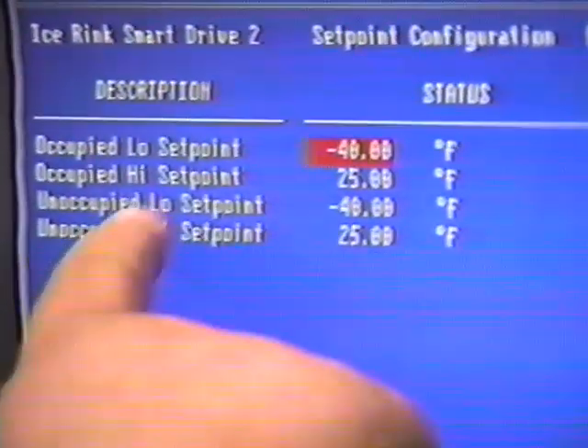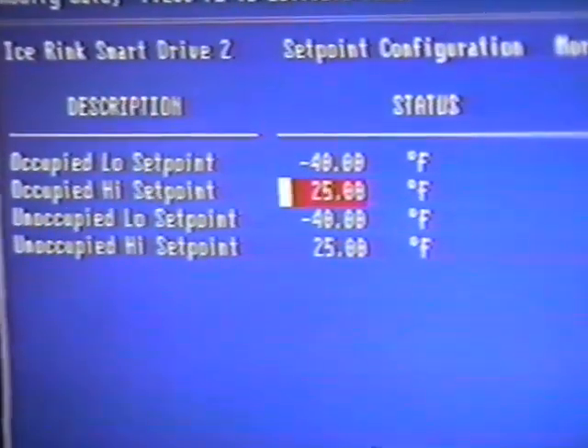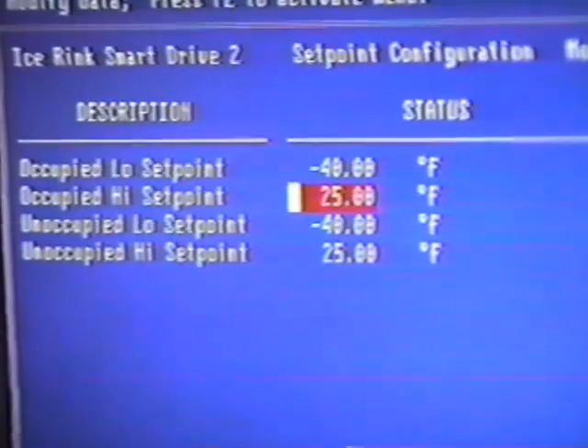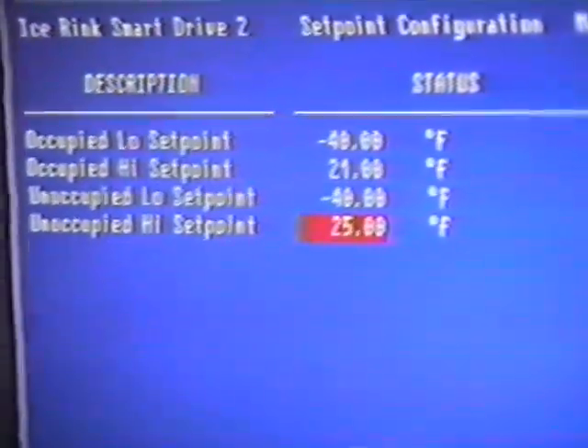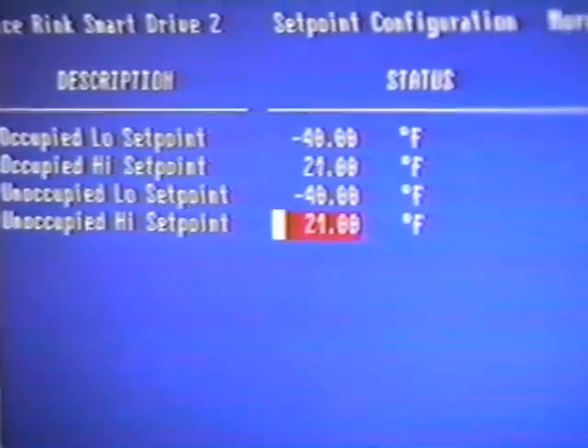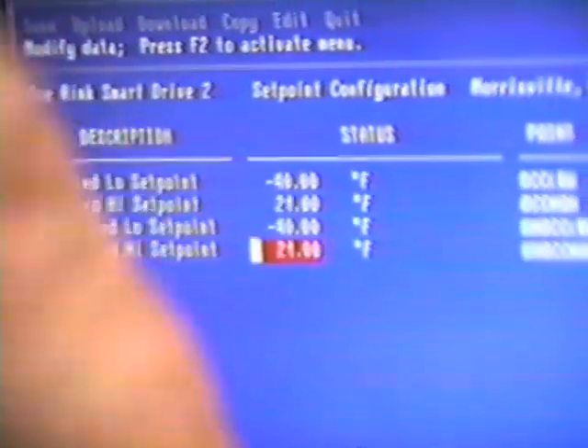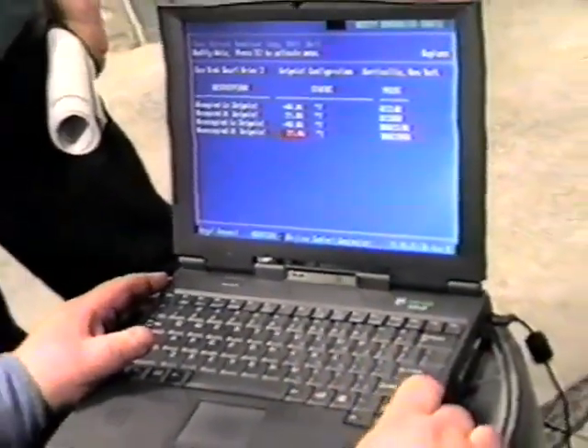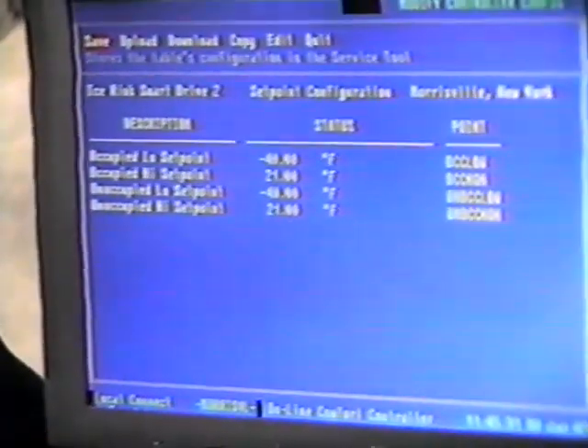Okay. All right. So we don't have any unoccupied mode, but for clarity, for the occupied and unoccupied high set points, we put our same temperature in. Whatever you want for ice temperature goes in there. You're going to be able to scroll down through, and say we were at 21 before: enter, enter, 21, enter. Now this one, I've got to send it over there, so I'm doing a little extra work. That one I don't think you're going to have to. Like I said, I'm not going to tell you for sure until I've done it. I have to send it, so now I've got to download it. There you go. And we go back to points, enter, enter, and then we can read it again.